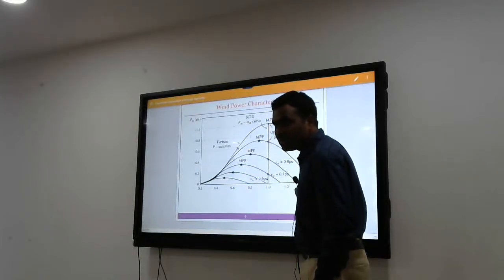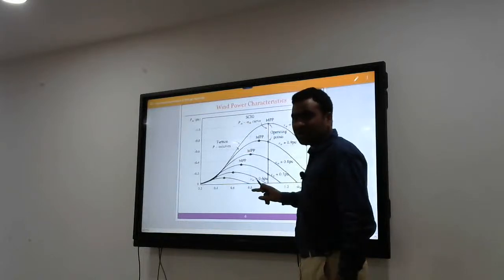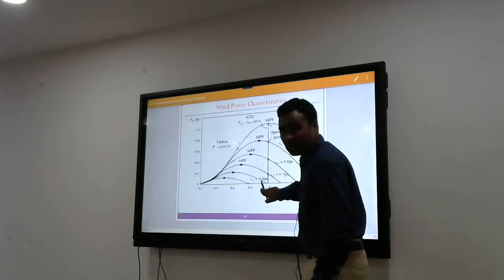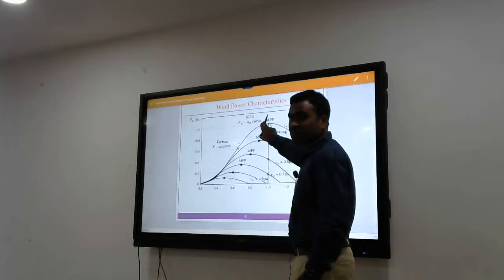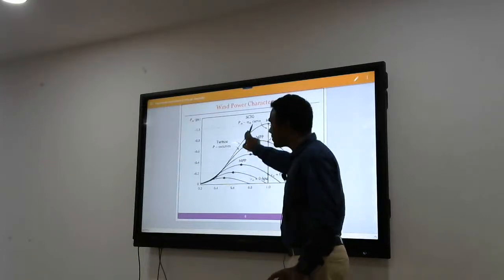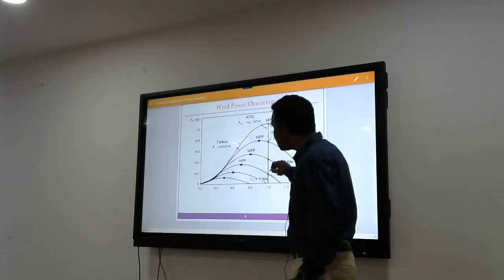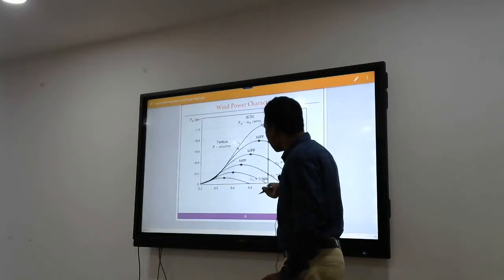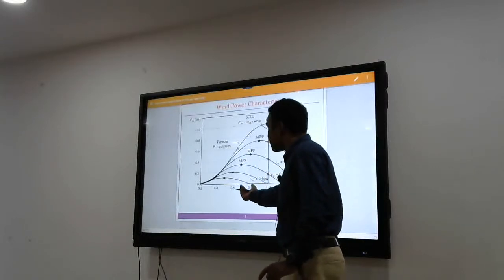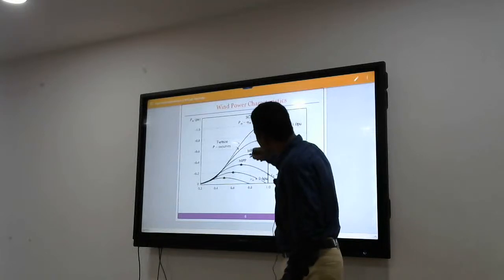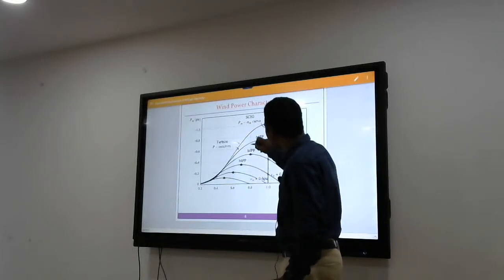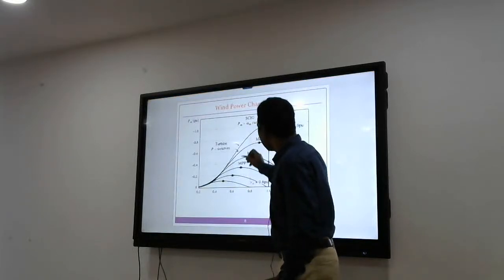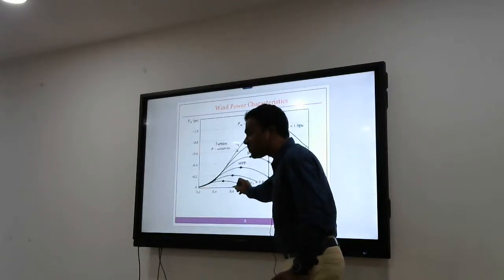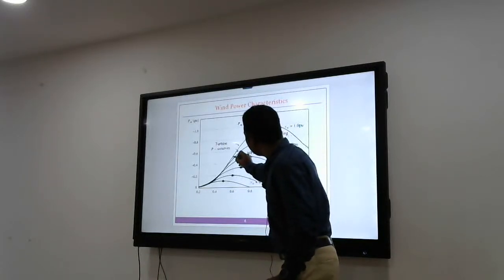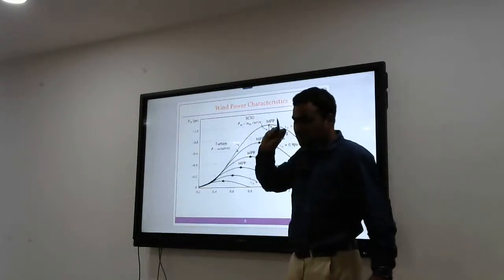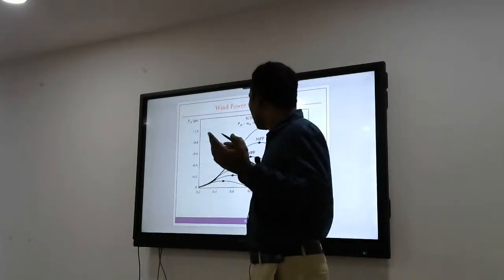I may get different powers based upon the rotor speed. Suppose I run my wind turbine at 1.0 per unit rotor speed, I will get this power. I'm repeating, my wind speed is constant, but if I change my rotor speed, my power changes. Sometimes it may be 1.0 per unit, sometimes 0.8. If I run my wind turbine at 0.8 per unit rotor speed, I may get this much power. If I run it at 0.6 per unit, I may get around 0.5 per unit. Okay, this is one thing.